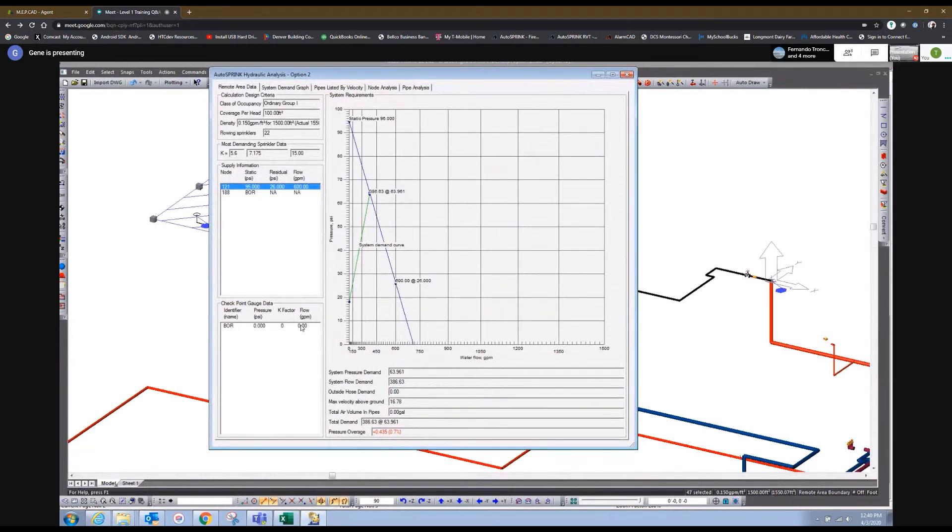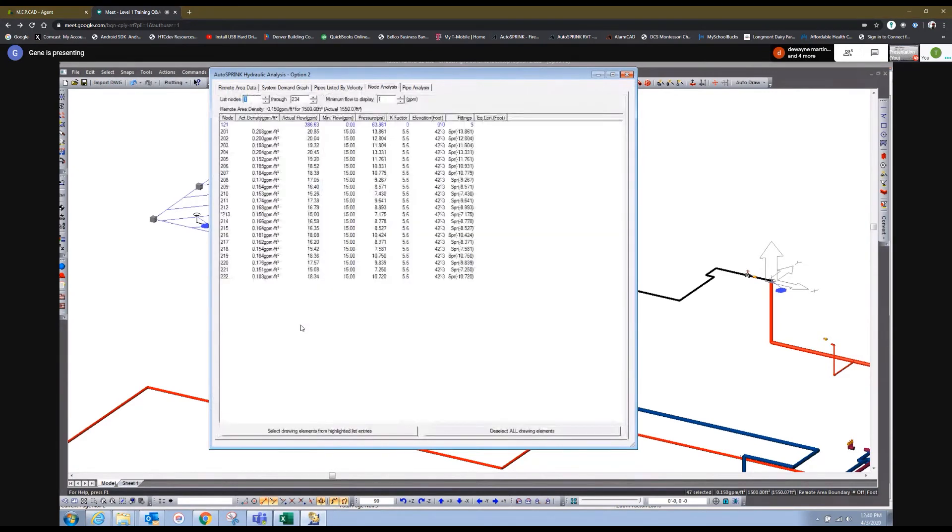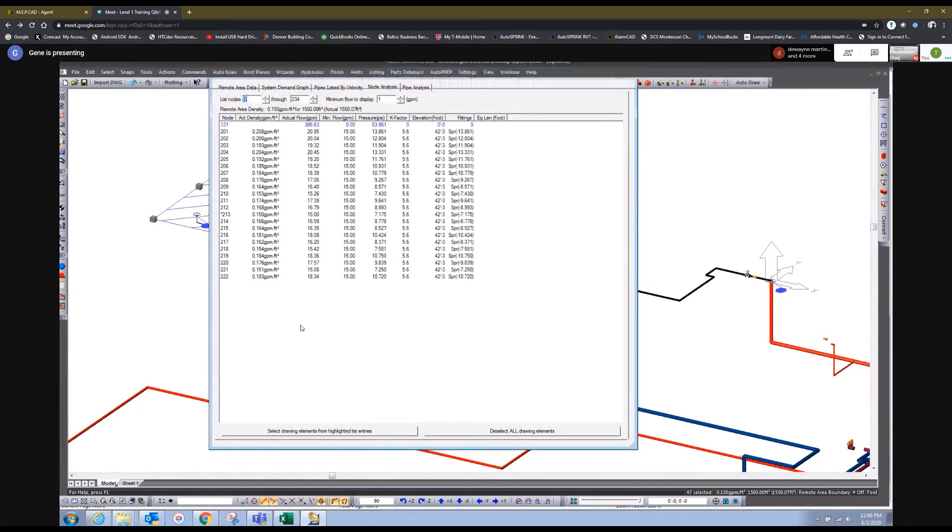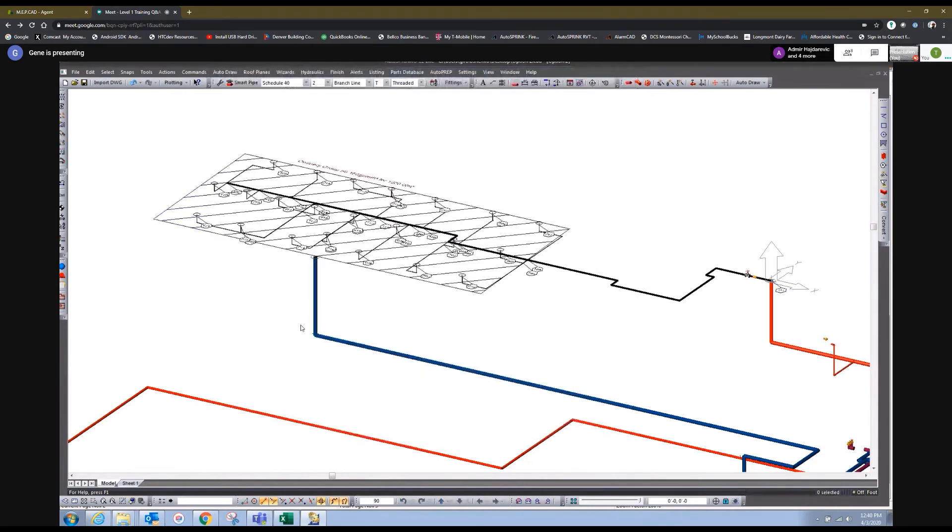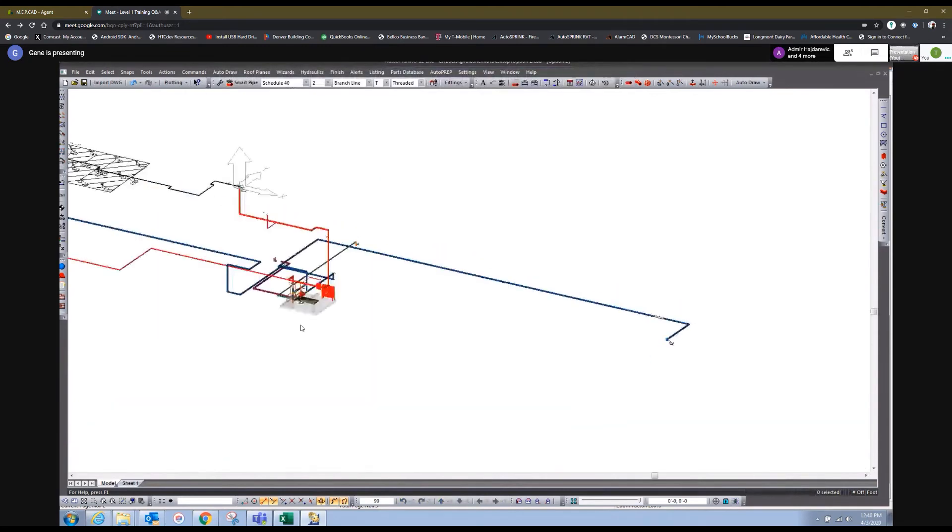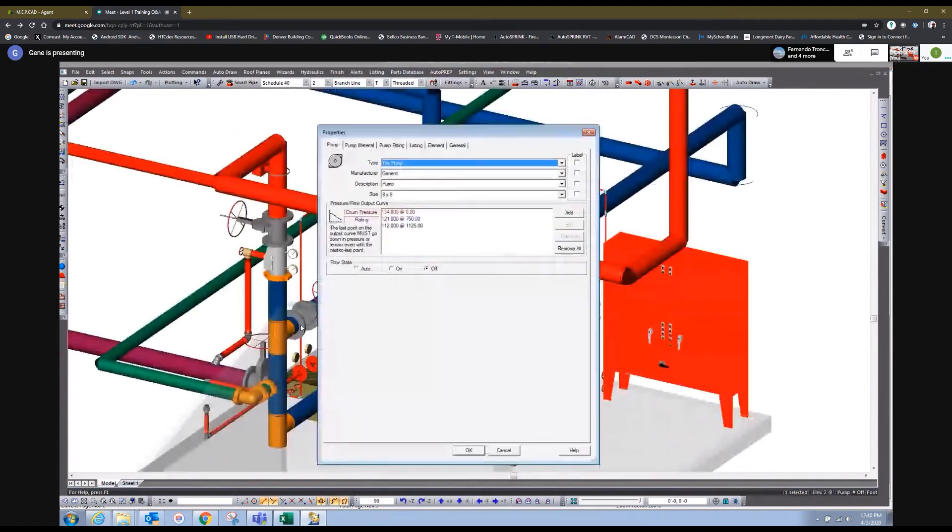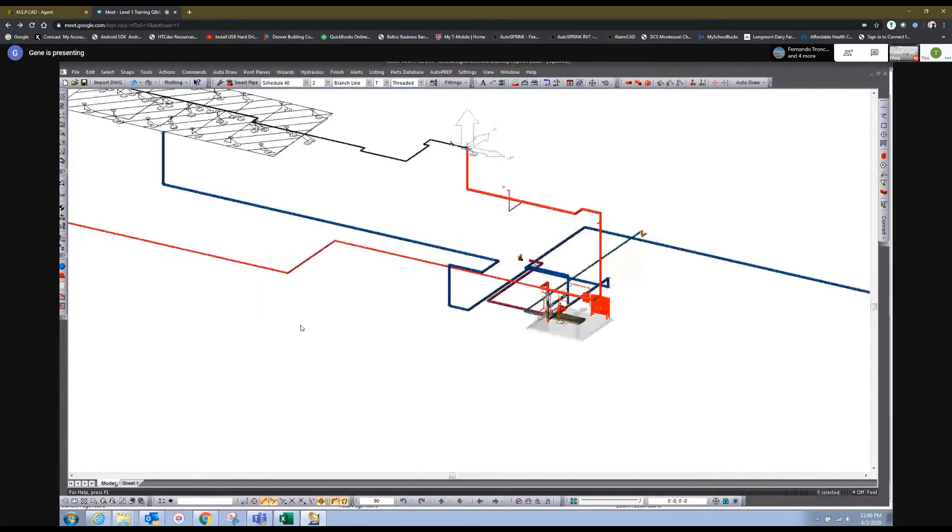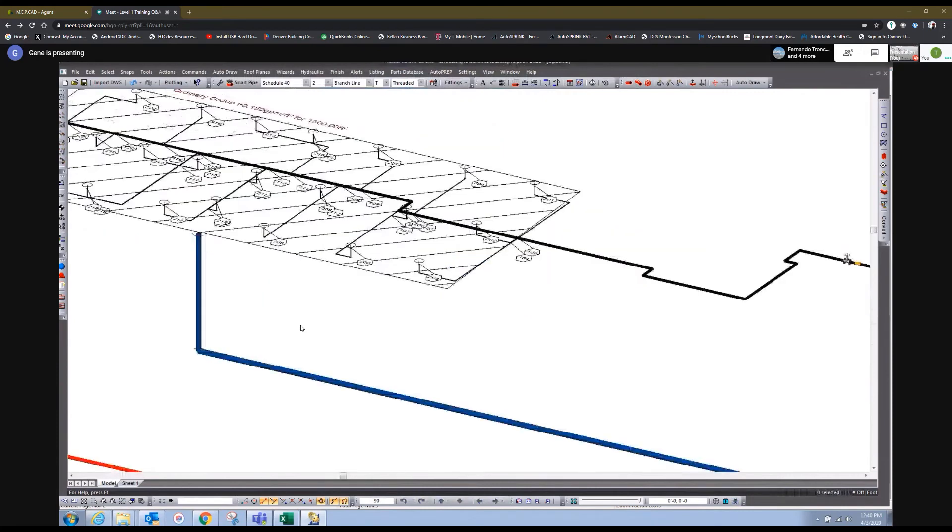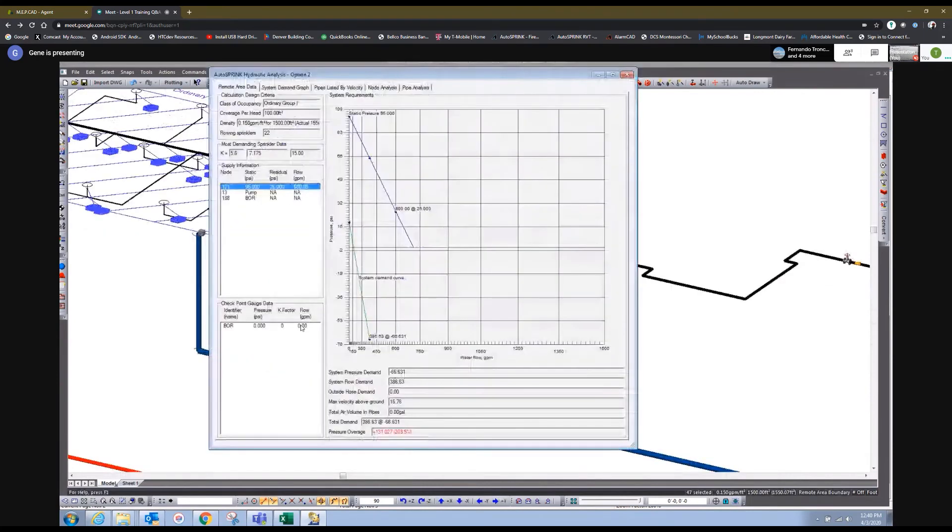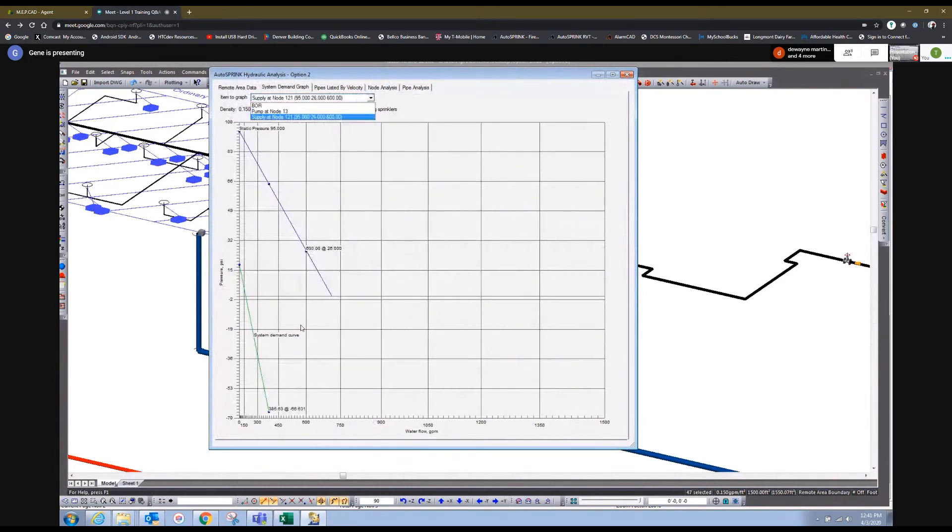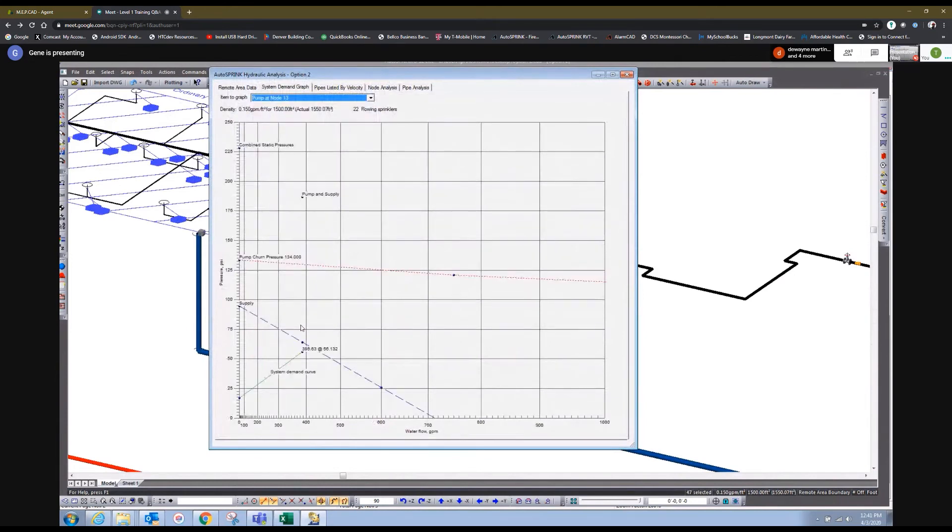And that's, you're saying this is the system demand at the, well, I guess, well, you're saying at the source, right? Correct. So, that would be 121, right? So, it would be basically right there, that's my source. But, when I activate the pump, hydraulic analysis, so you get all this. Now, it says negative 66. Yes, sir. But, if I switch to pump at node, it gives me, like, 56, which is now, I guess, we discussed that it's at the pump.